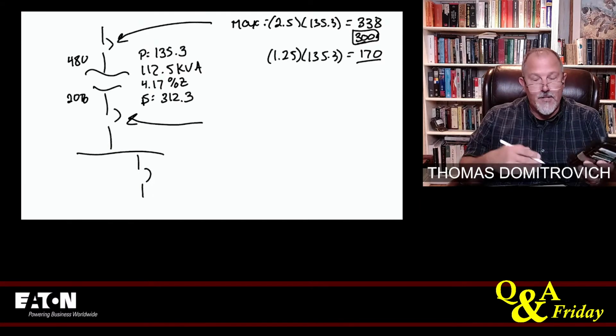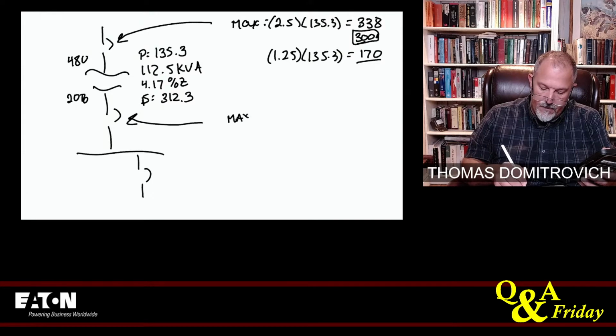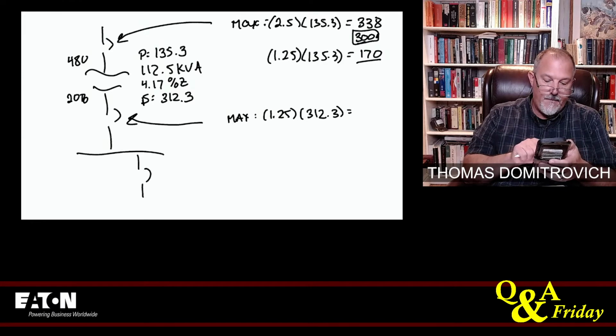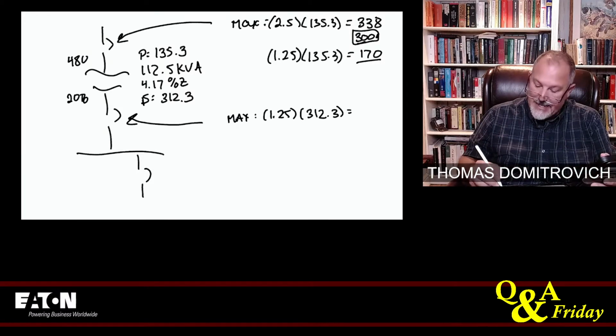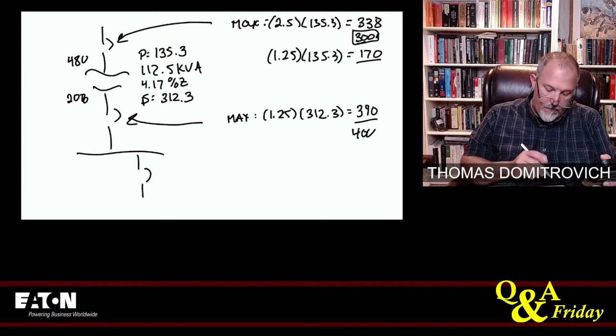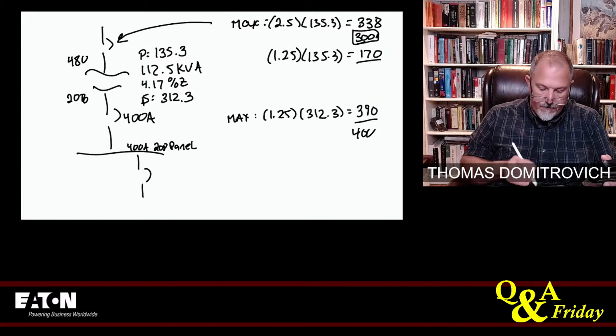All right, secondary. I have primary and secondary protection. I'm always going to have secondary protection. So my maximum based on the table is 1.25, remember, we're looking back in Article 450, times 312.3. So 1.25 times 312.3 is 390. I can go to the next higher, so I can go 400. So I'm going to make this a 400 amp, and this is a 400 amp 208 panel board. And we'll take a look, and we'll probably try to make that maybe a 200 amp.